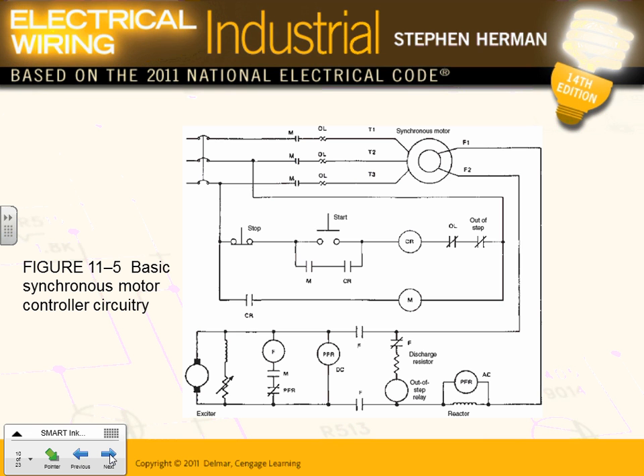Okay, here's how a synchronous motor works. A lot of you have heard of DC motors, a lot of you have heard of capacitors. When you use a synchronous motor, what they put right here is DC. By increasing the voltage, let's just say 50 volt, here I'm just throwing this one to 150 volt DC, they are adjusting the voltage here. They're putting more or less voltage. The more voltage you put here on this synchronous motor, the more VARs the synchronous motor starts creating. That's how a synchronous motor works.